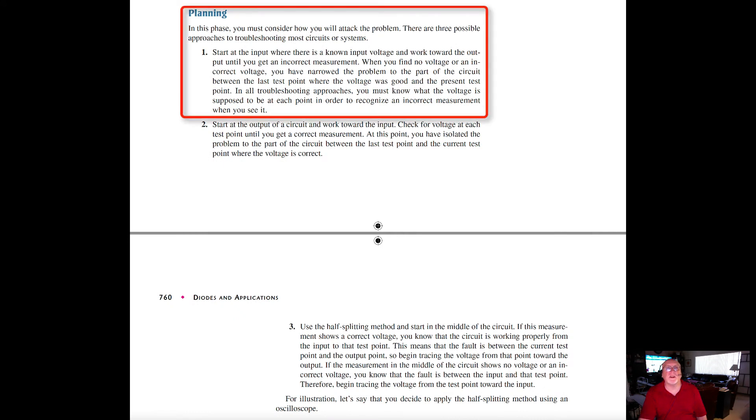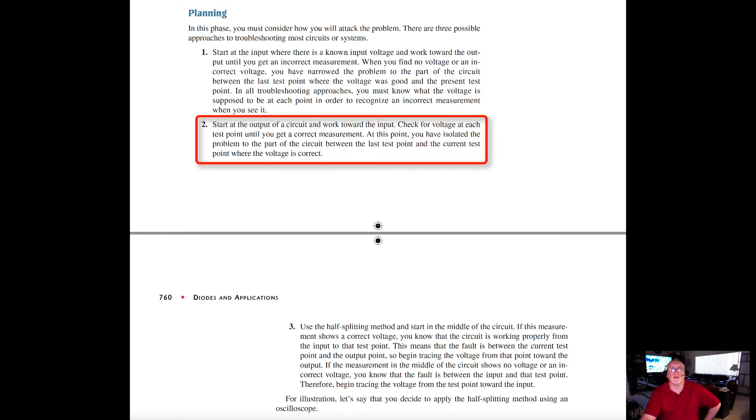In the planning phase, start at the input where there's a known input voltage and work toward the output until you get an incorrect measurement. When you find no voltage or an incorrect voltage, you will have narrowed the problem to the part of the circuit between the last test point where the voltage was good and the present test point. In all troubleshooting approaches, you must know what the voltage is supposed to be at each point in order to recognize an incorrect measurement when you see it. Start at the output of the circuit and work toward the input. Check for voltage at each test point until you get a correct measurement. At this point, you've isolated the problem to the part of the circuit between the last test point and the current test point where the voltage is correct.